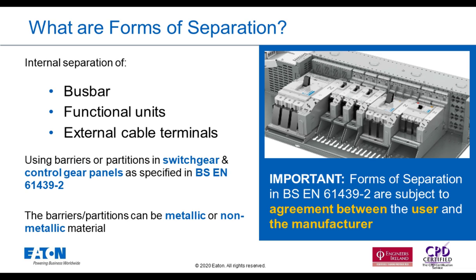So there are three main components that we look at when we're looking at forms of separation. First being the bus bar. This is normally your main bus bar or distribution bus bar. Functional units are normally your protective device, so this could be your ACB, MCCB, or a fuse switch. And external cable terminals. These are what I would call the terminals where the customer connects his cables on to. And internal separation, again, we achieve this using barriers and partitions. These could be metallic or non-metallic.